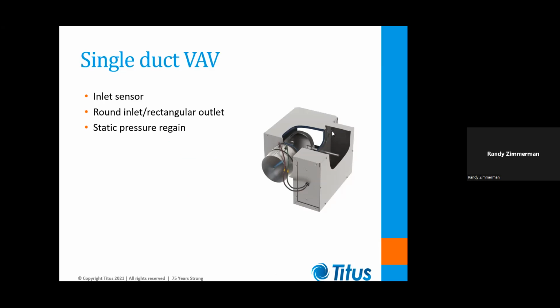You'll notice that the configuration of this unit has a round inlet and a rectangular outlet, and that's not by accident. When Titus pioneered this type of design back in the 1970s, we always tried to make the discharge connection at least twice the cross-sectional area of the inlet. And the idea there is that as air flows over the damper and then expands to fill the casing of the unit, we get some static pressure regain in there, and that lowers our static pressure requirement to the room.